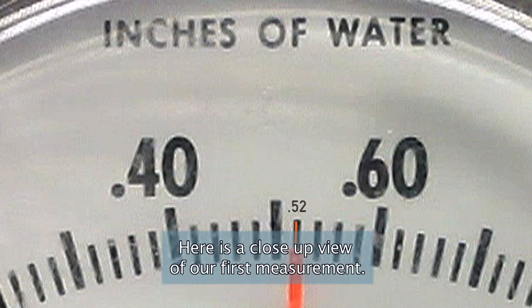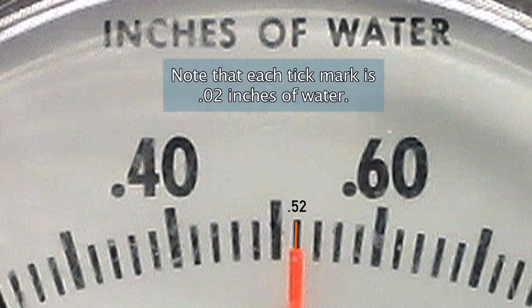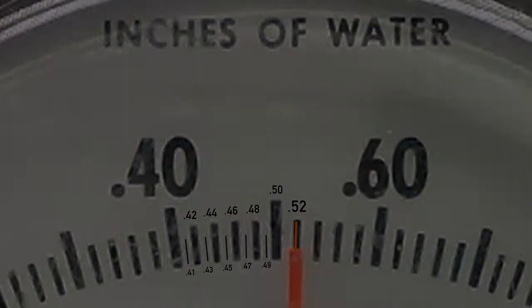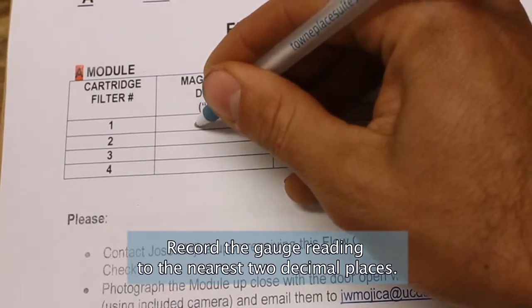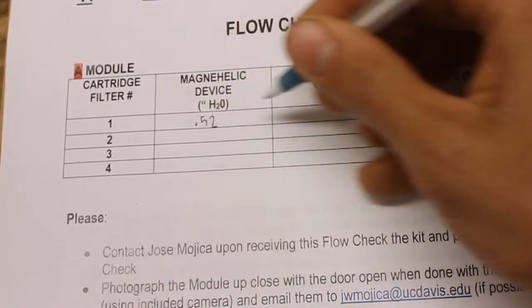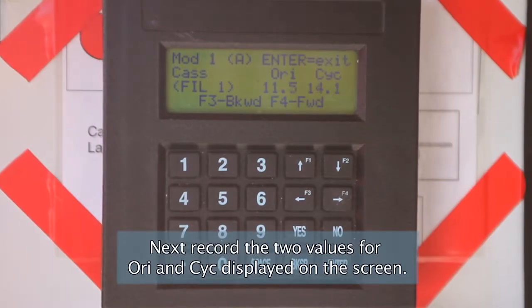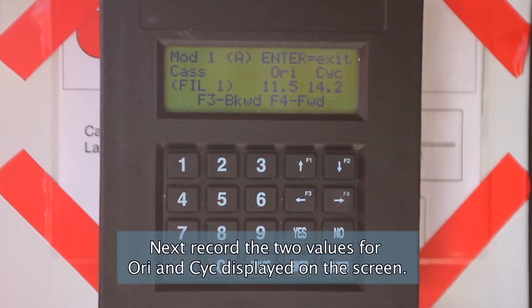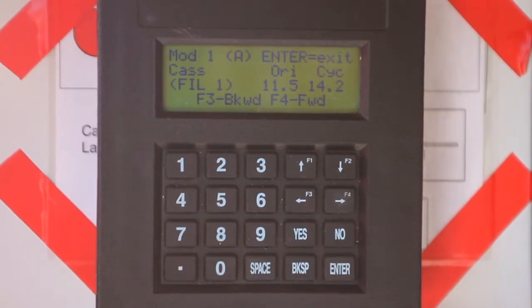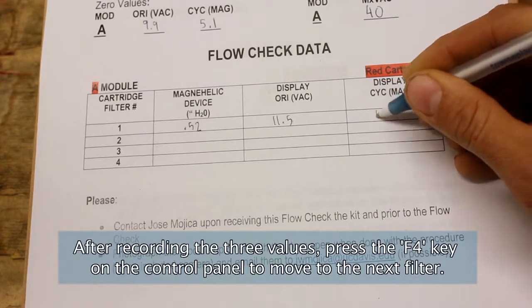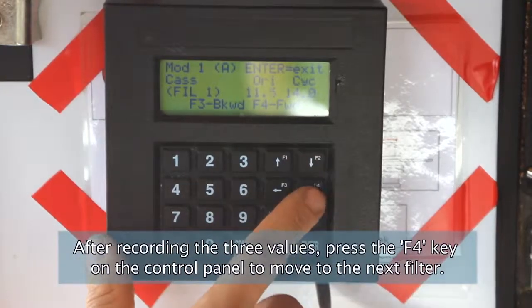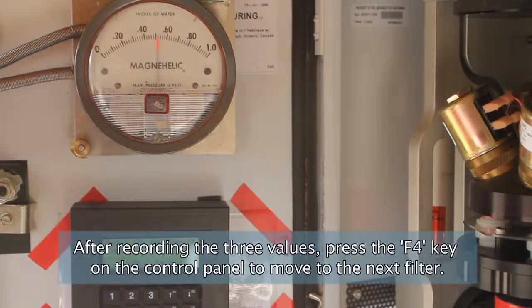Here is a close-up view of our first measurement. Note that each tick mark is 0.02 inches of water. Record the gauge reading to the nearest 2 decimal places. Next, record the 2 values for ORI and CYC displayed on the screen. After recording the 3 values, press the F4 key on the control panel to move to the next filter.